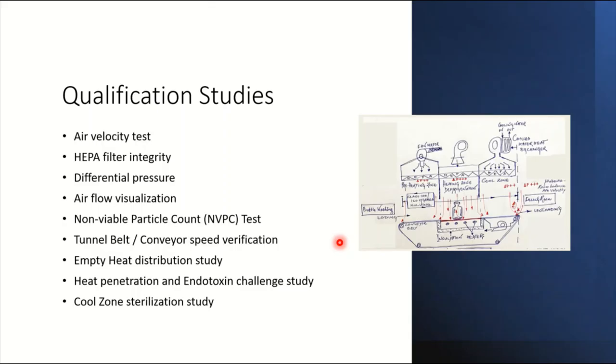We will not talk too much on this slide as we have detailed description in the upcoming slides. Just running through the tests: air velocity, HEPA filter integrity, differential pressures within the room and zones, airflow visualization studies—normally recommended, a few years back people were not doing this. Non-viable particle count, yes we are claiming ISO 5, so we should prove that the area is getting passed and fulfilling the requirements of ISO 5.